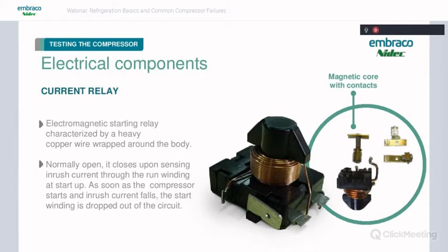As soon as that compressor starts up and that heavy inrush current falls off to normal running current, gravity is going to pull this plunger down and de-energize the start winding. So it's a very simple device the way it works. You see this a lot because it's so simple.